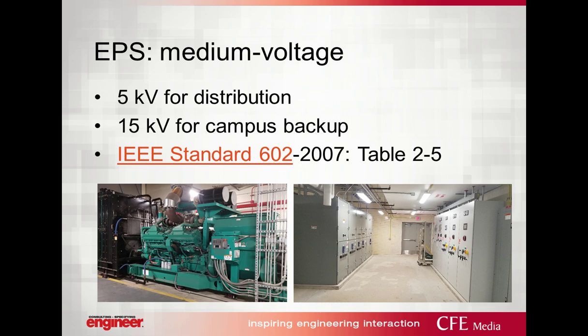The other question I see quite often is, should we use medium voltage generators? I personally, if I have a large hospital campus or a large campus in general, and I need to distribute from a central utility plant, I'll strongly consider a 5 kV generator set, which means you're going to have unit substations placed in each one of your buildings for emergency power distribution. And we'll typically see these as parallel gear. The photo on the right is 5 kV parallel gear.